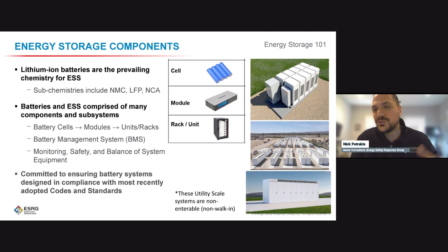These codes and standards, as David mentioned, there's a lot on here—it's a lot of alphabet soup. But the reason I put this up is that there are multiple layers of safety, multiple mandatory requirements if you're looking to install any of these systems. It goes all the way from the base level, the module design, the cell design and testing, to the larger energy storage system, UL 9540 and 9540A, which covers full-scale fire testing.